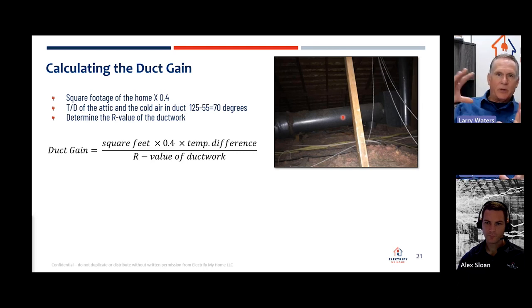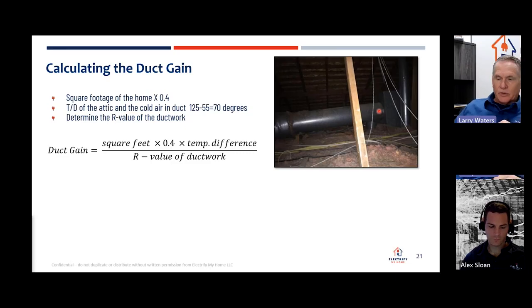And it gets to be 125 degrees, very conservatively, in the attic space, and you've got raw metal there. That return air turns into a heater. So now all of the air that's coming through that return air is getting preheated before it goes into the system, and the system has to use a specific amount of its capacity to offset that. It's the same with the supply side.